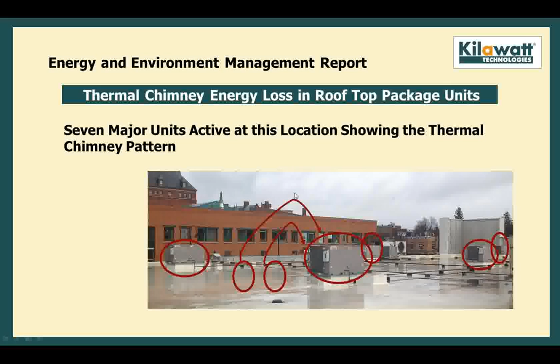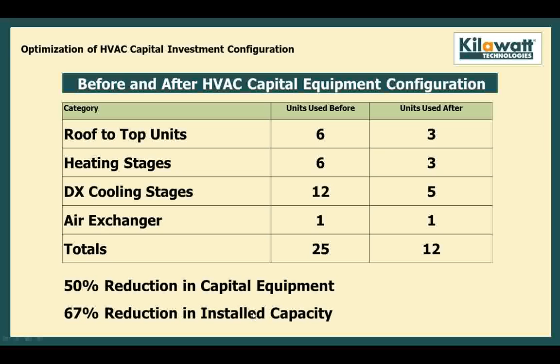In summary, of the rooftop units, we're going to take their 6, reduce it to 3. We've already reduced it to 2, but we're going to drop another one out. Heat stages available, we're going to take it from 6 to 3. The amount of cooling, 12 stages to 5. A total reduction of 50% of the capital equipment, and a reduction of 67% of the installed capacity. And they will still have more than 100% redundancy in this system.